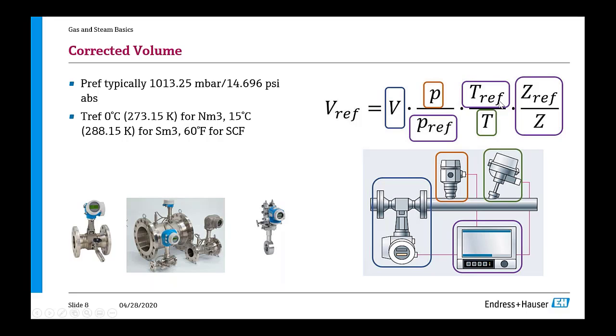For normal meter cubed, that's 0 degrees C, so 273 kelvins. Here it's important that you use kelvins if you do the calculations yourself. Otherwise you have a wrong term. So this is highly important. And then they measure temperature again in kelvins. Flow computers and so on will do the conversion themselves. And here you have the relation of the compressibility factors, at reference conditions to operating conditions. The reference temperature, by the way, for standard is 15 degrees C, or for standard cubic feet, it's 60 Fahrenheit.